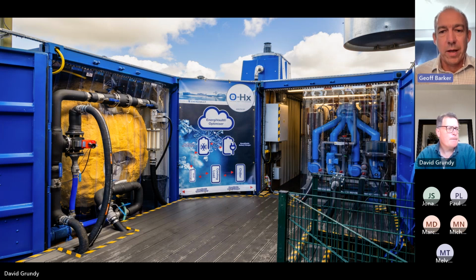The charger is typically 50 to 60 kilowatts refrigeration, and they store nominally up to about a megawatt hour of thermal storage, depending really on the duration in which you charge the system. So in this particular configuration, you could charge it for 20 hours to get a megawatt hour, or you could have 2 chargers in a similar system and charge it in 10 hours. So quite a modular system, and basically producing a considerable amount of daily available cold energy to optimize existing systems.